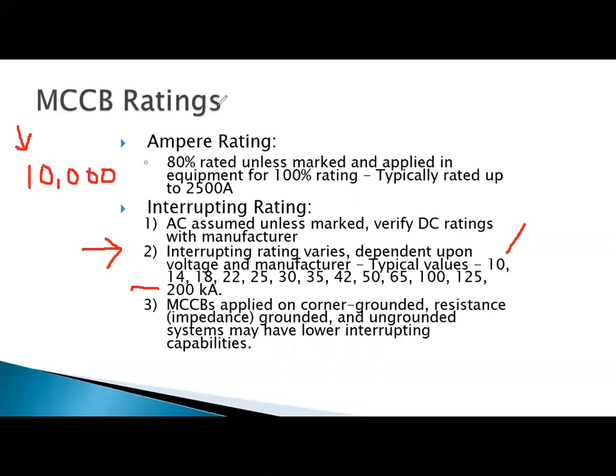Because we have a federal law in OSHA 1910 that says my interrupting rating has to be greater than whatever the available fault current is. I told you at this hotel I'm at today, the fault current was around 23,000 amps. And that's true. That means that my interrupting ratings on my circuit breakers better be higher than that.